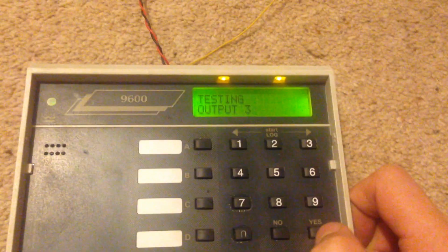Very simple. So then output one, wherever that is, the transistorized output, would be energized, and so would this. These only give 125 milliamps. These give 1 amp at 24 volts. So for example, if you had a 24 volt bell that you wanted to use, I know my school would. So that's output three and then four.